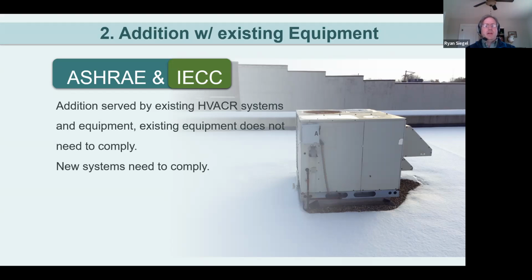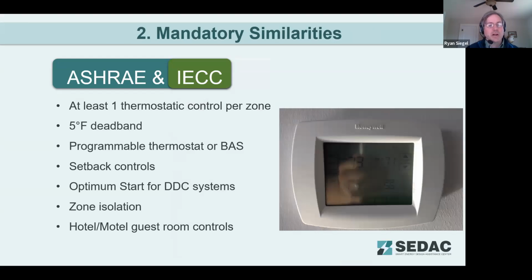So this can be kind of handy, as Sean alluded to earlier, that oftentimes we find HVAC equipment does have reserve capacity remaining on it, either from initial oversizing or perhaps upgrades that have been made throughout the building, lighting and plug loads that now have some reserve capacity that can be extended. So it's kind of nice that if you're going to extend that ductwork, they don't require you to go ahead and upgrade your HVAC unit. They say, no, your existing one is fine. Just go ahead and make sure your ductwork is good.